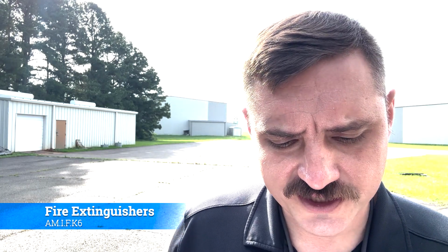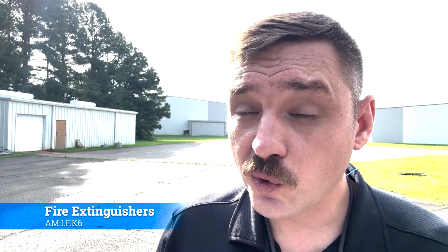Okay, let's talk about the inspection of fire extinguishers, something that you will do. So first off, there's a couple things we're going to look for anytime you're doing a fire extinguisher inspection. First off, whatever document is driving you to inspect that fire extinguisher, be it an AMM, some sort of local procedure or whatever, most likely it's going to have the best information for what that fire extinguisher inspection entails. And so follow that. If you're doing a generalized kind of fire extinguisher inspection, these are the things that you're going to be looking for.